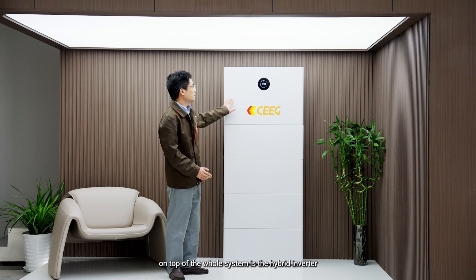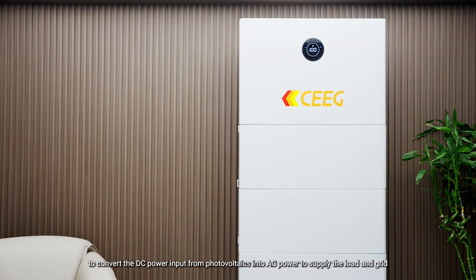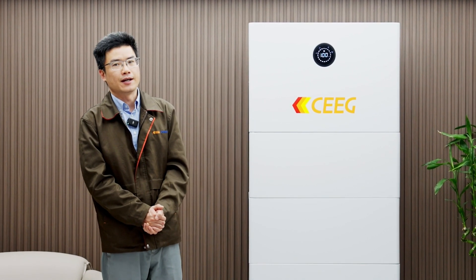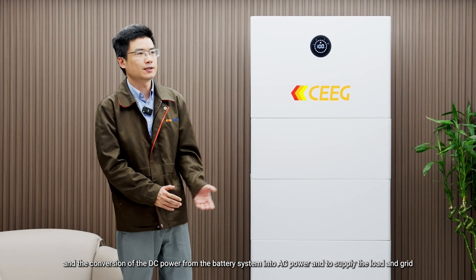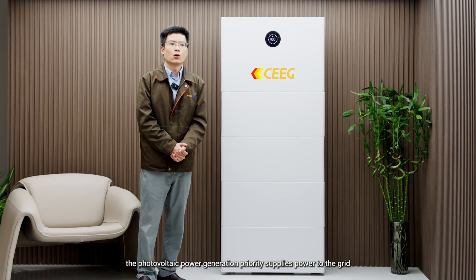On top of the whole system is the hybrid inverter. Its main functions include DC to AC conversion, converting the DC power input from photovoltaics into AC power to supply the load and grid, and conversion of the DC power from the battery system into AC power to supply the load and grid. There are three main working modes. First of all, the self-consumption mode.